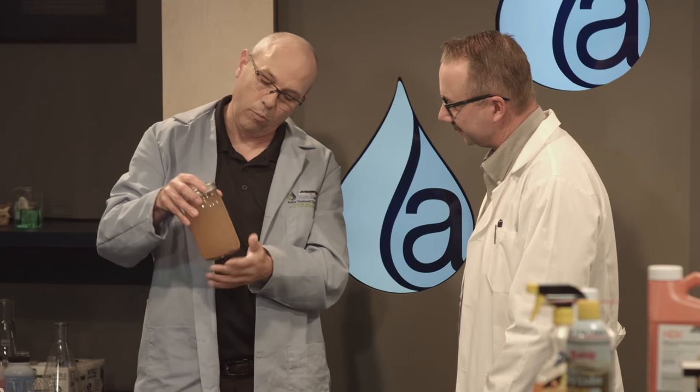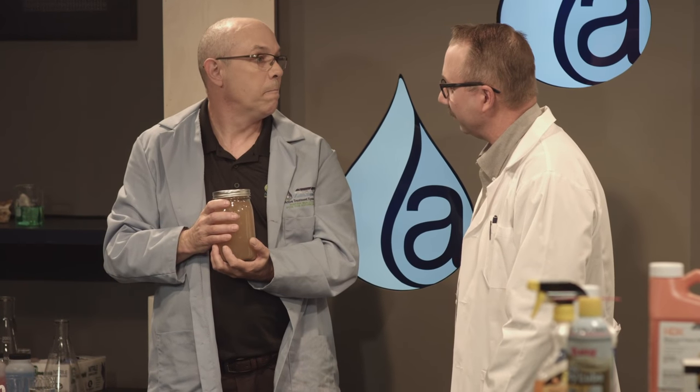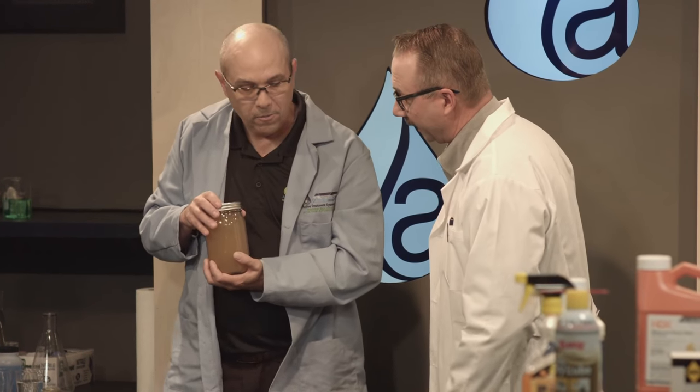For the most part, this turbidity is going to be well over the 250 limit where we could discharge. This was probably in the range of a thousand NTU when mixed up — I took a turbidity reading and it was over 1,000. In fact, our meter doesn't even go that high — it goes to 1,000, so I had to dilute the sample.